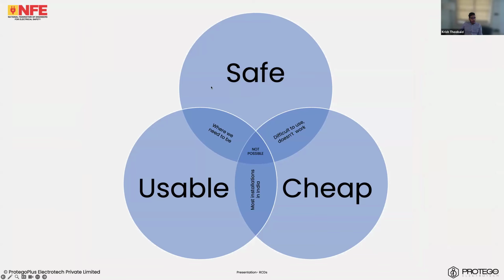I am here to tell you, you cannot get an installation that is safe, usable, and cheap. It's not possible. We can have an installation that's usable and cheap. This is most installations in India, but the installation is simply not safe. We can also have an installation that is safe and cheap. You can take one type B RCD, put it on the entire building. The moment you turn some electronic equipment on, the RCD will trip. They're perfectly safe, but you have no electricity to use, so the installation is completely unusable. Where we need to be is safe and usable.